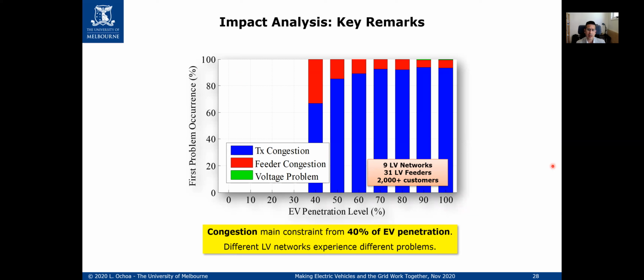When you actually look at multiple low voltage networks, which is what we did in this particular project, what we found is that yes, the transformer is the first to suffer, shown in blue, at around 40% penetration, 4 in 10 houses with an electric vehicle. Then the feeders get congested as a second problem, and voltages are not necessarily a significant problem in this particular case. Again, this is specific to Britain because of the characteristics of the networks, but the transformers suffer immediately because of the aggregated currents. Of course, these are cars that are not being managed.